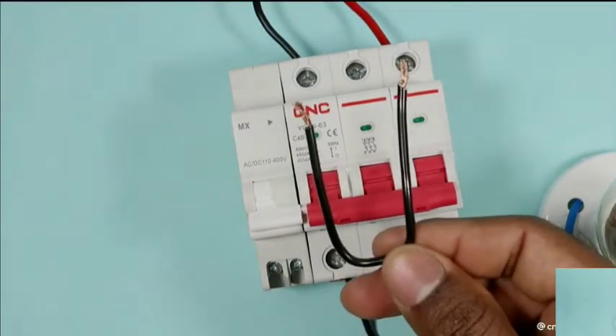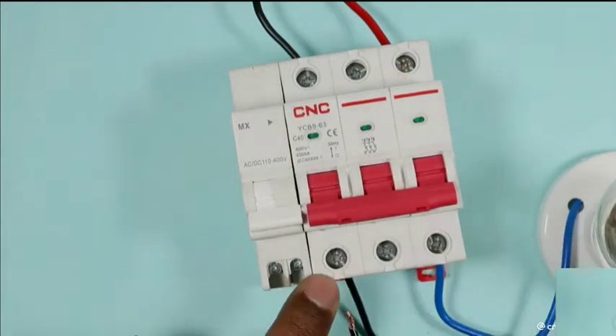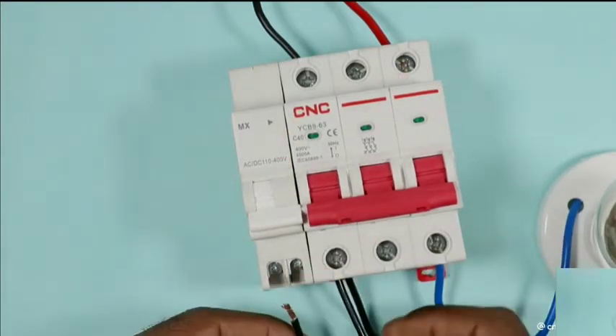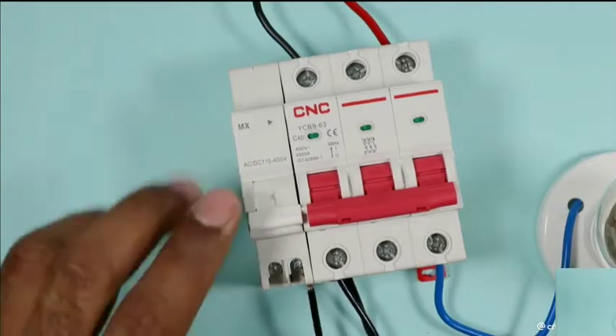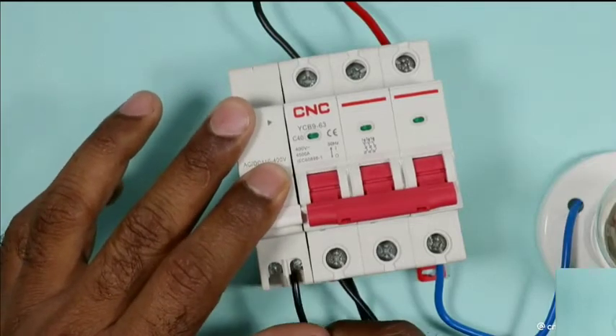I am using this piece of wire. Connect one end with neutral power supply of MCB and connect other end with one terminal of shunt coil. This is how connection must be done.